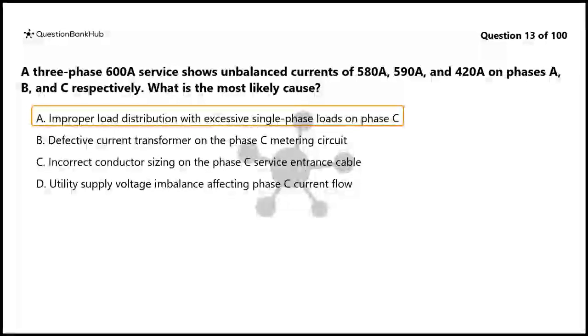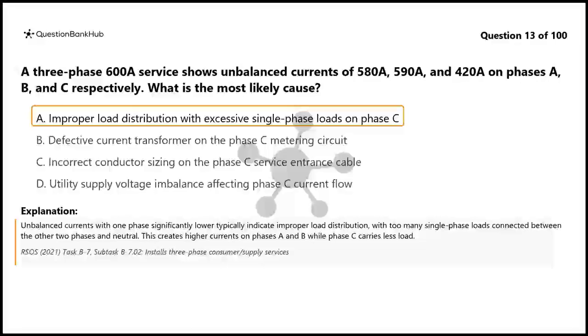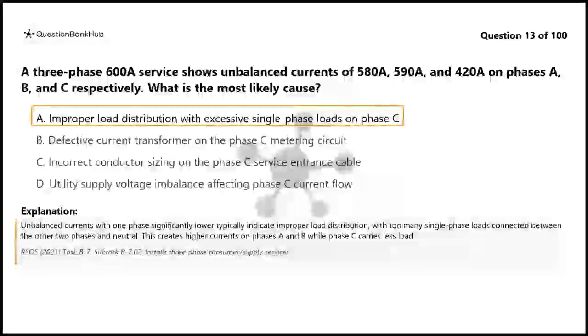The correct answer is A. Improper load distribution with excessive single-phase loads on phase C. Unbalanced currents with one phase significantly lower typically indicate improper load distribution, with too many single-phase loads connected between the other two phases and neutral. This creates higher currents on phases A and B while phase C carries less load.